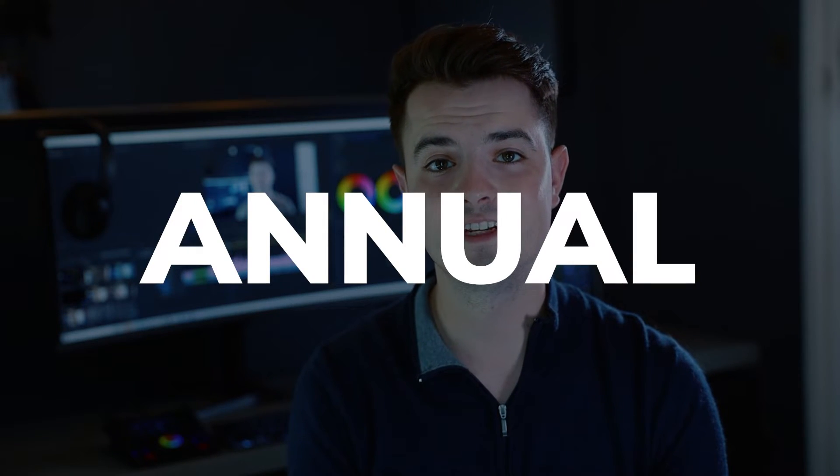On a yearly basis, tests need to be arranged for annual inspections. These need to be carried out by a competent person. Defects must be logged and the necessary actions taken and recorded. A certificate of testing and maintenance should be obtained. There's a complete list of what needs attention in BS9999 2008 Annex 5. This periodic inspection and maintenance needs to be carried out to check for any unmonitored faults, take preventative action, and ensure the continued reliability of the system. It's also important to make sure the user is aware of any changes to the building which may affect the protection that the system was designed to give.